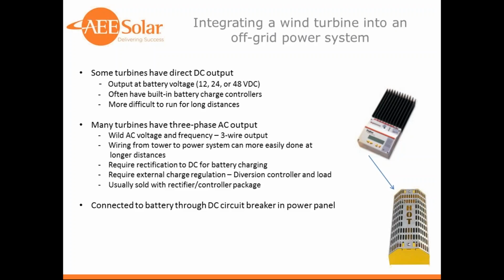Then there are many turbines that just produce a three-phase AC output, with wild voltage and frequency, usually three-wire. It's not generally usable directly because the wind blows at variable speeds, so the turbine spins at variable speeds, giving huge variation in frequency and voltage. So you can't have a three-phase wind turbine run a three-phase load directly—that's really not going to work out.